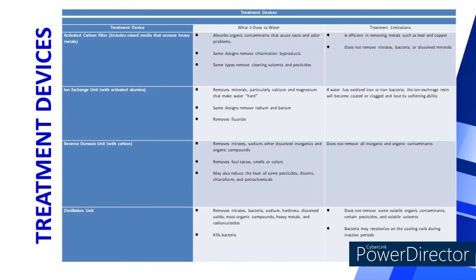Treatment Devices: Activated carbon filter — includes mixed media that removes heavy metals. It absorbs organic contaminants that cause taste and odor problems, some designs remove chlorination byproducts, and it sometimes removes cleaning solvents and pesticides. Limitation: efficient in removing metals such as lead and copper, but does not remove nitrates, bacteria, or dissolved minerals. Ion exchange unit / Activated alumina — removes minerals, particularly calcium and magnesium that make water hard; some designs remove radium and barium; and it removes fluoride.